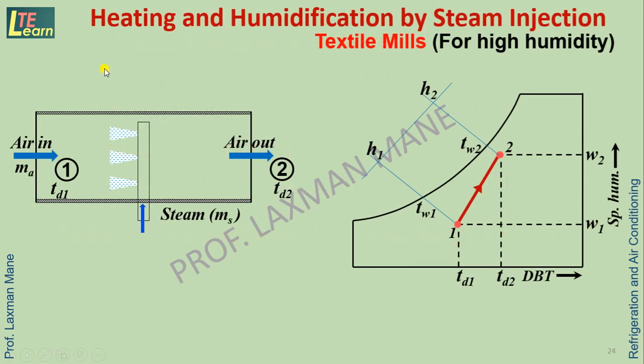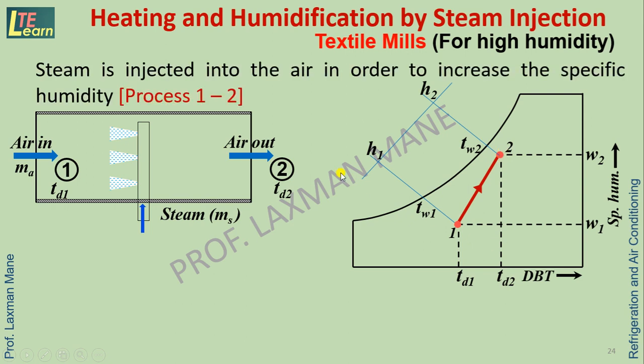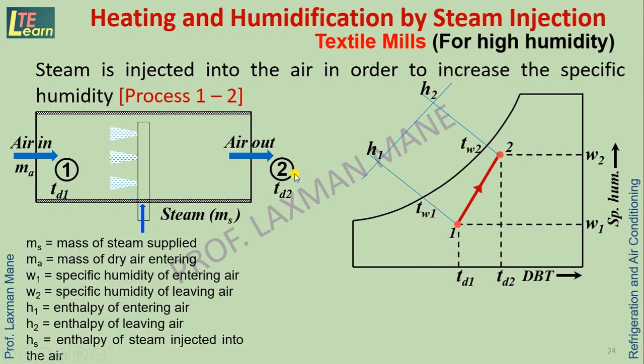Heating and humidification by steam injection is used in textile mills for higher humidity requirements. This process is done by steam injection into the air, with steam supplied at a rate of Ms. Air enters at state 1 and exits at state 2, as shown on the psychrometric chart by process 1 to 2. The key parameters are: Ms — mass of steam, Ma — mass of dry air, W1 and W2 — specific humidity at inlet and outlet, H1 and H2 — enthalpy at inlet and outlet.